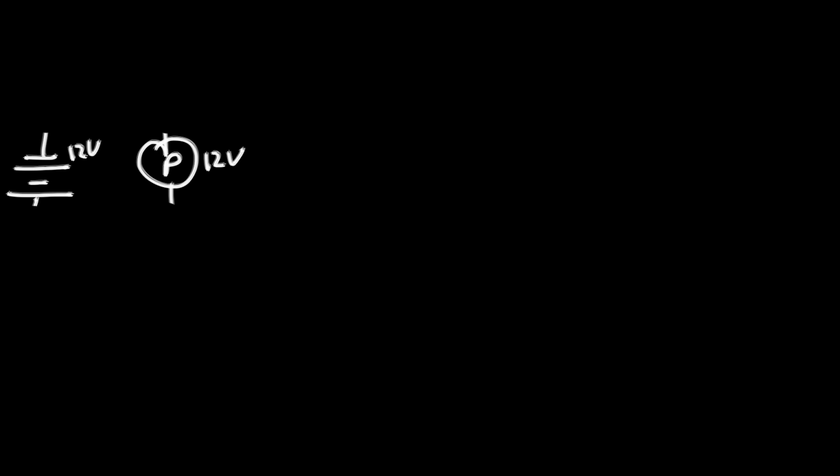But it's not really the case, because you have to imagine that the wires are super long resistors, and I'm losing some volts in those wires. This means that I don't have 12 volts at the pump. So this is the formula to find the voltage drop in a wire. To calculate this voltage drop, I need 4 variables.